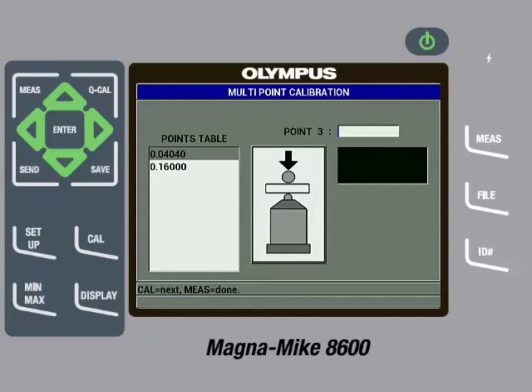86W-CAL-010 reference standard. Then we will loosen the cap and insert the wire into the slot on the side of the fixture and then screw down the cap until it is secure. We will then place it on the probe and pull down gently on the calibration fixture. The instrument will start displaying a measurement. Once the reading on screen is steady, we will press the cal key.